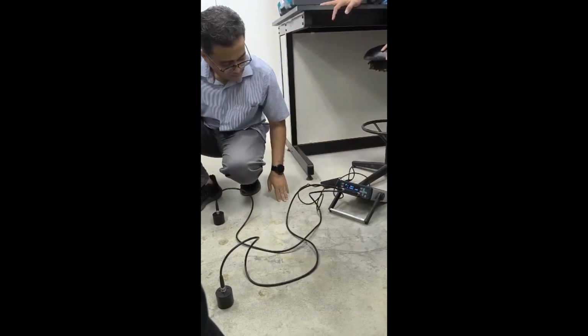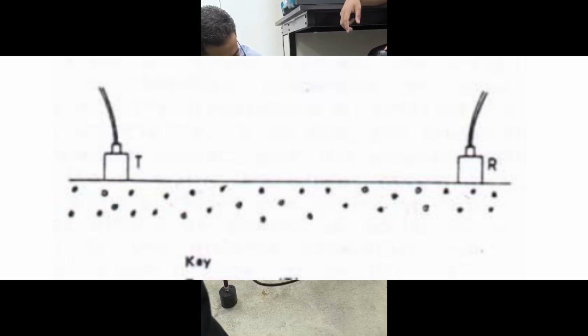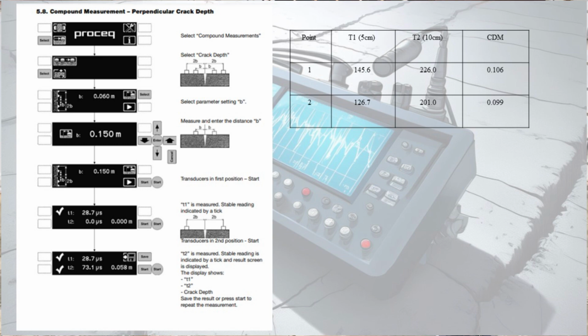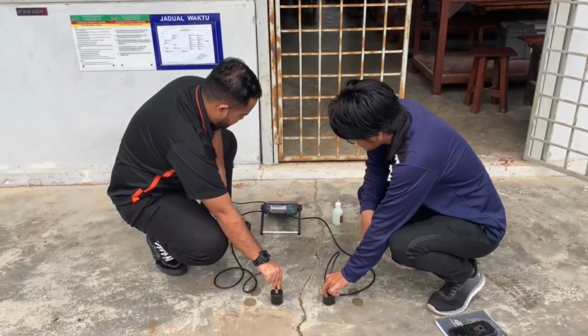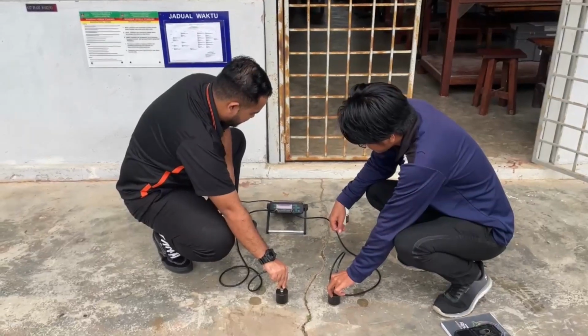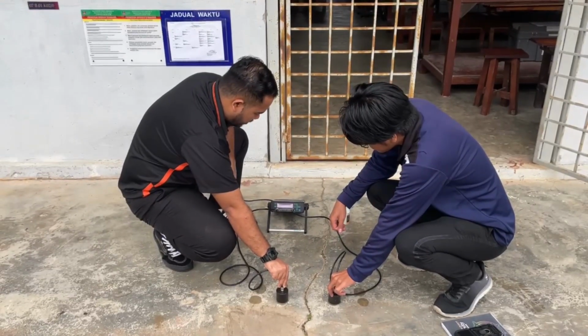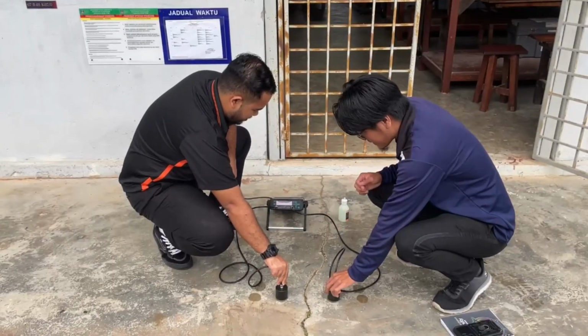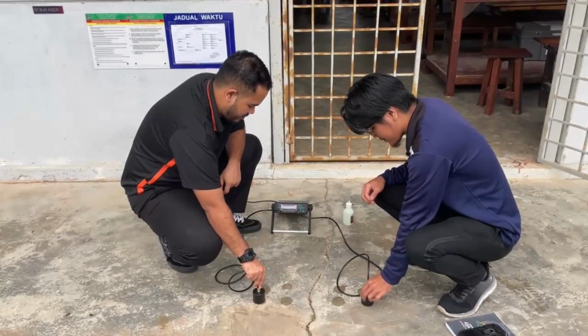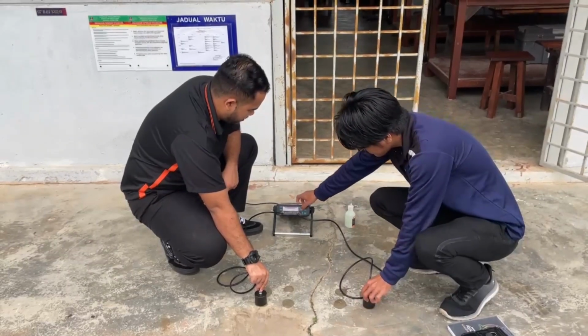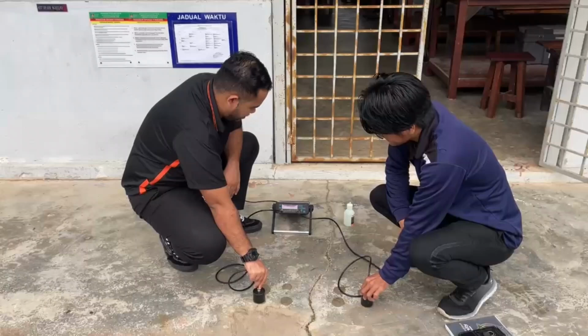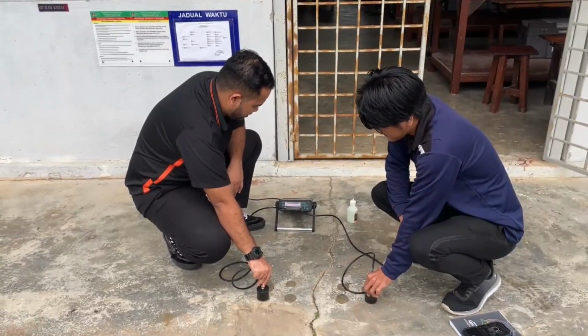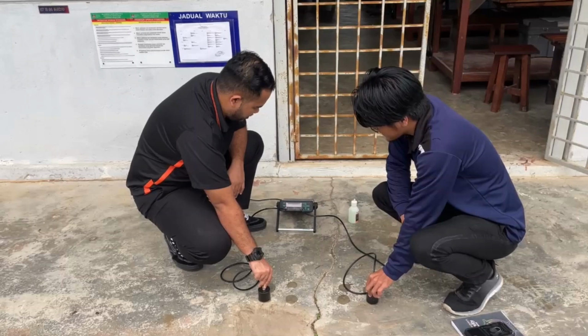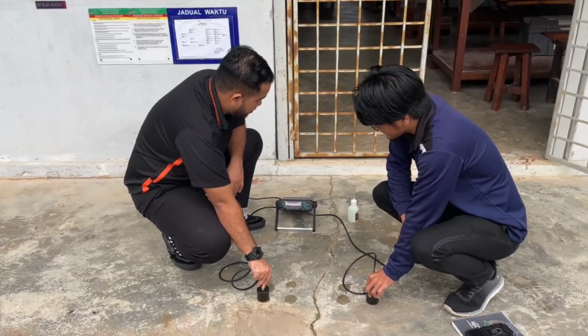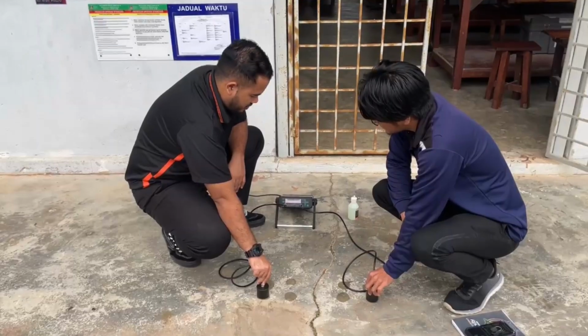Using the surface transducer position, record the data in order to collect the data of compound measurement, perpendicular crack depth using the equipment. Follow this step: select compound measurements, and then crack depth. Set the parameter B and measure the distance. Place the transducers in the first position and press Start to measure T1. Move the transducers to the second position and press Start to measure T2. The display will show T1, T2, calculated crack depth. Save the results or repeat the process as needed.